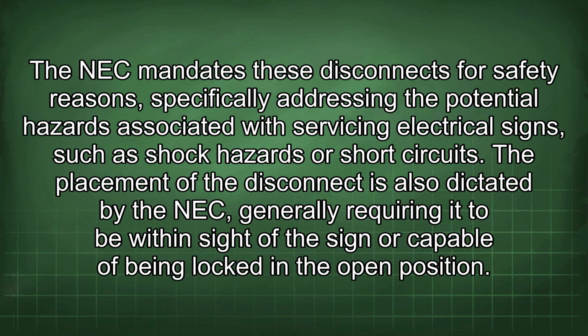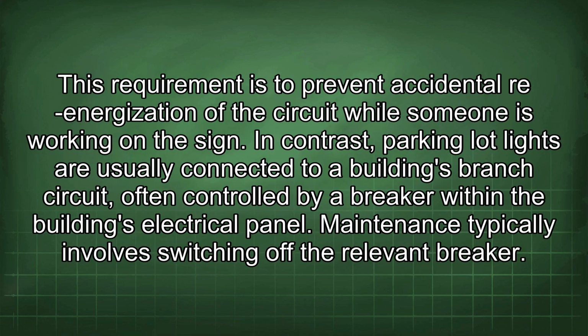The NEC mandates these disconnects for safety reasons, specifically addressing the potential hazards associated with servicing electrical signs, such as shock hazards or short circuits. The placement of the disconnect is also dictated by the NEC, generally requiring it to be within sight of the sign or capable of being locked in the open position. This requirement is to prevent accidental re-energization of the circuit while someone is working on the sign.